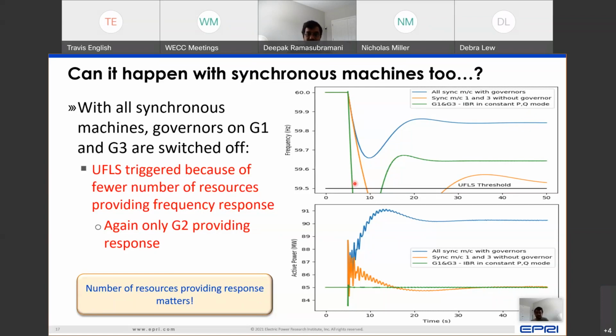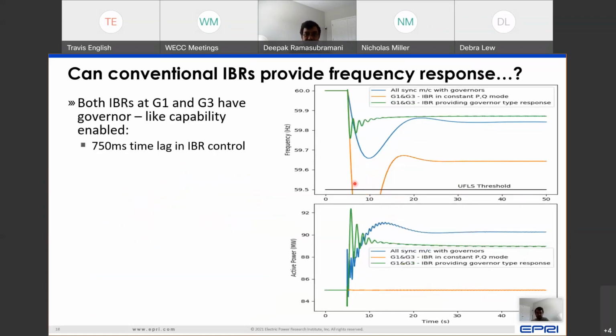Because if you take the same setup, the same example, and you make an inverter-based resource provide primary frequency response with governor-like capability, and even if you assume there is a 750 millisecond time lag inside an IBR control so that it has time to calculate frequency and then react to it, even with that, by default these IBRs do not have a mechanical time constant. There are no turbines involved. There are no governors involved. So there are no mechanical time constants involved, at least in solar and battery. Wind has mechanical time constants, but that's also something that can be dealt with. But let's assume here that you have solar and battery.